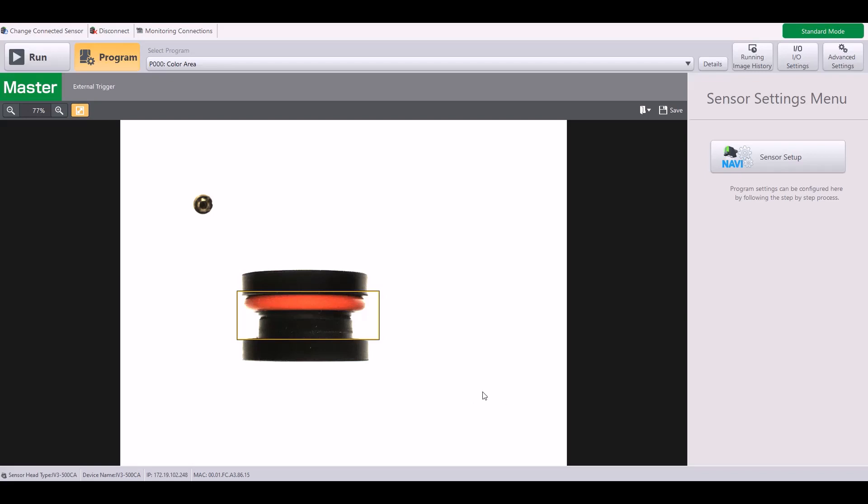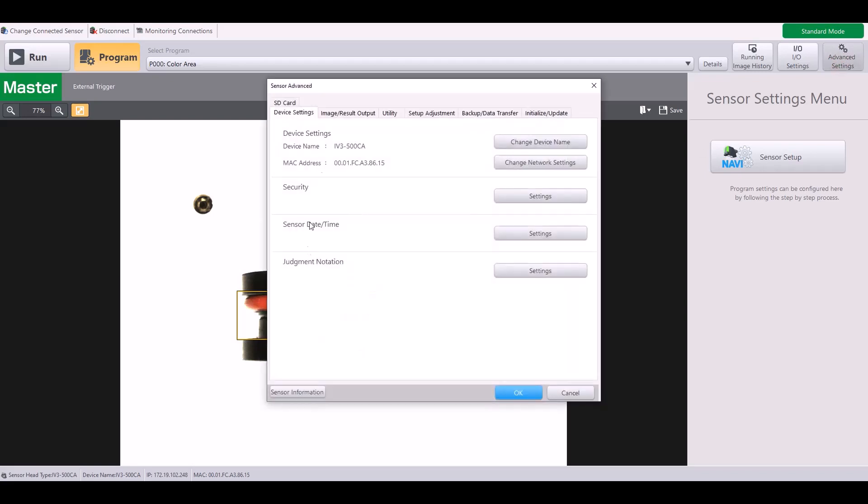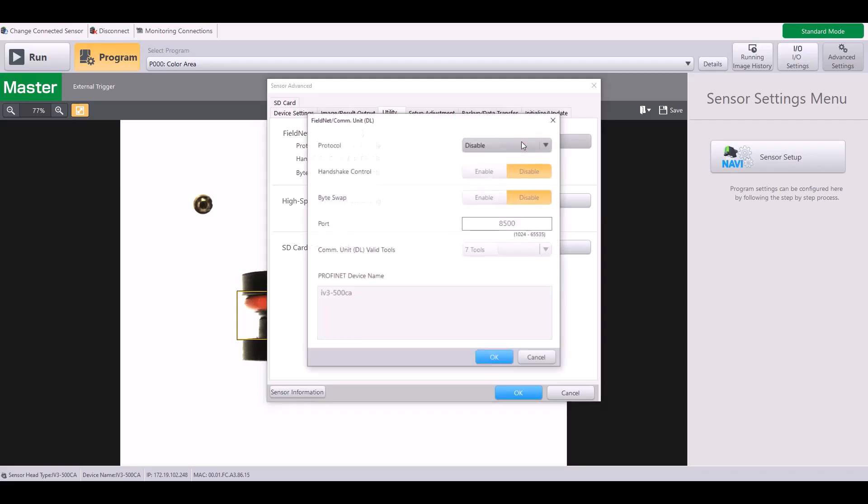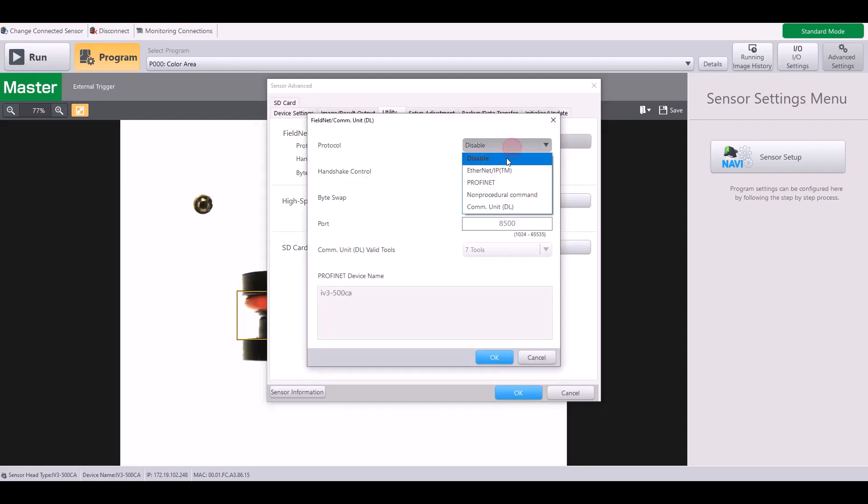there are a few settings in IV3 Navigator that need to be adjusted. As you can see, I am currently connected to an IV3, and the first thing we're going to do is go to Advanced Settings and the Utility tab. Here is your field network or communication unit protocol, and as you can see, the default is disabled. We need to hit Settings and go ahead and enable Ethernet IP.